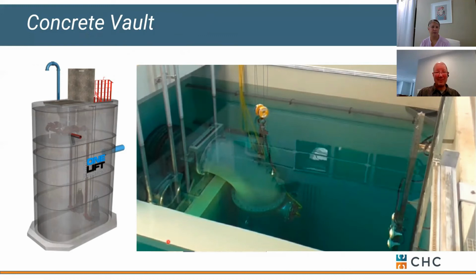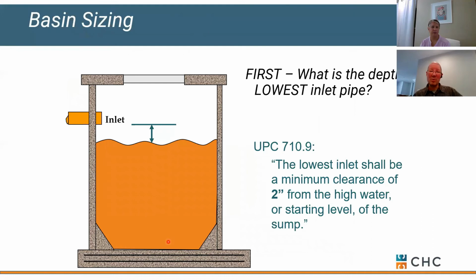Obviously clean water. Some rules of thumb as far as basin sizing. We can never back water up into our inlet, or what a lot of people call an invert. This is clearly where water is coming in from our building, whether it's groundwater or sewage, depending on the application. But we never want the ability or want to back water up into that invert. We have to keep that clear.